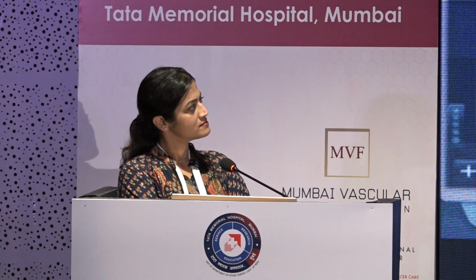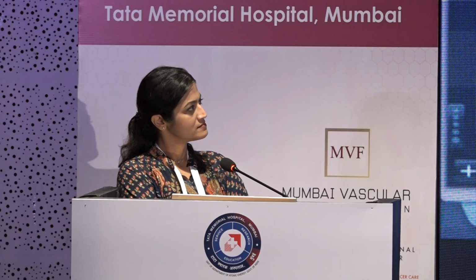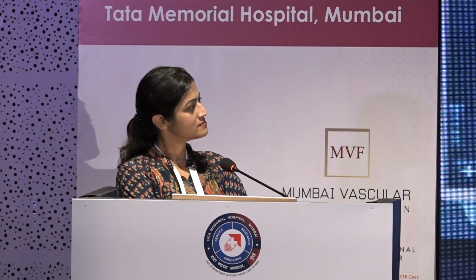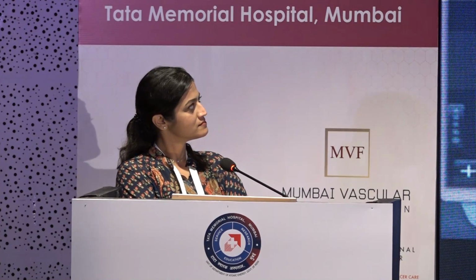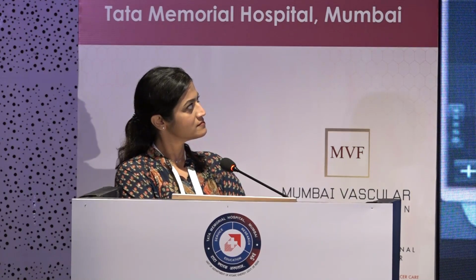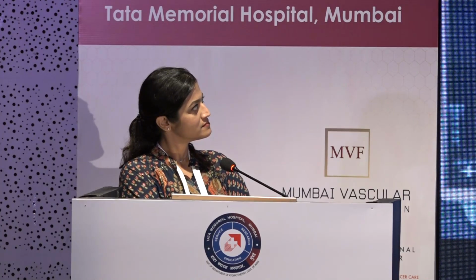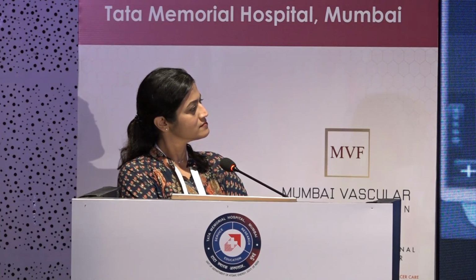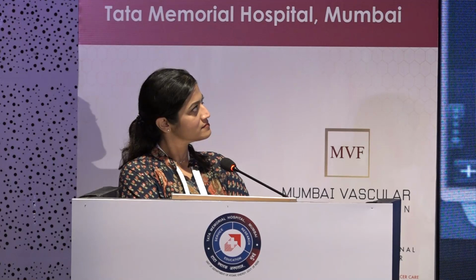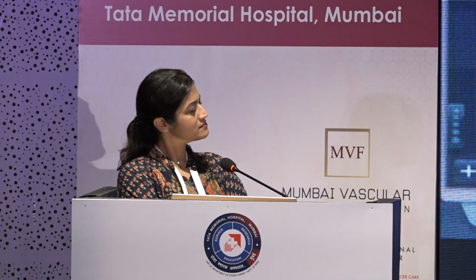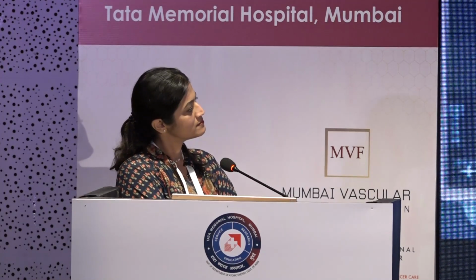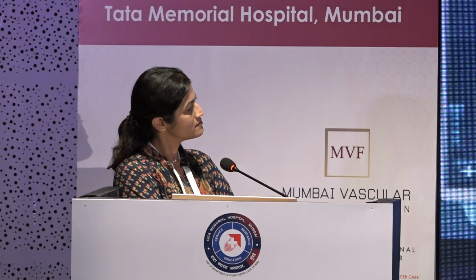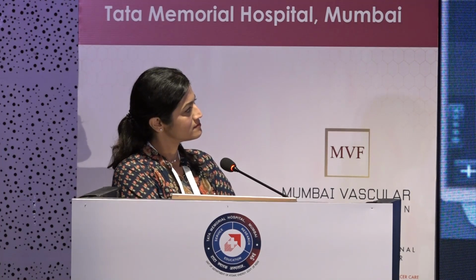We are now going to see if I'm able to acquire the whole of the breast in anterior-posterior acquisition. I am comfortable with the position and the contact which I could see on my end. I'll start the acquisition. I am applying some manual pressure so that the breast tissue lies flat. In case I need any assistance, there is an assisted compression mode which I would use. If you could see on the bottom right part of the screen on your left, there is a small dome-shaped thing. Once I compress, it just goes down. It will just give the idea of compression given there. Once I'm comfortable, I'll start the acquisition.